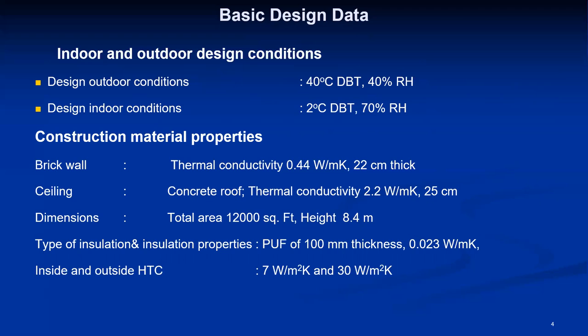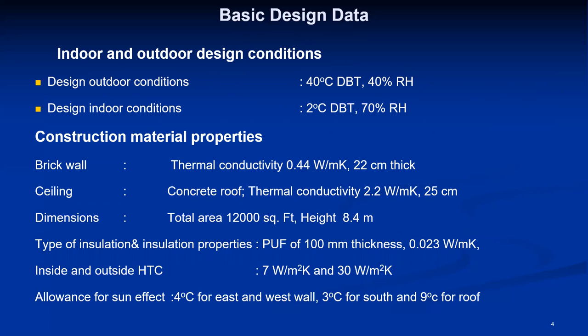The insulation recommended is 100 mm thickness with thermal conductivity 0.023 Watt per meter Kelvin. Inside heat transfer coefficient is 7 Watt per meter square Kelvin, while the outside heat transfer coefficient is 30 Watt per meter square Kelvin, slightly higher to account for windy conditions. The allowances for sun effects are: 4 degrees Celsius for east and west walls, 3 degrees Celsius for south, 0 degrees Celsius for north, and 9 degrees Celsius for the roof. Maximum solar transmission happens through the roof, followed by east, west, and south. No heat transmission takes place from the north side.